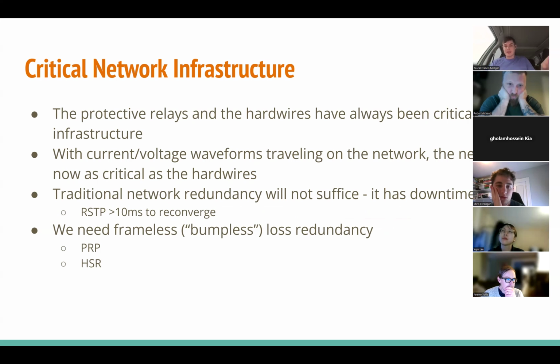So we have things that can handle that: PRP and HSR, which I briefly mentioned last class. Utilizing these two technologies on an Ethernet network, you can make it so that even if you have a single point of failure, you never lose even one frame. That's why we can utilize an Ethernet network for protection signals in a digital substation.